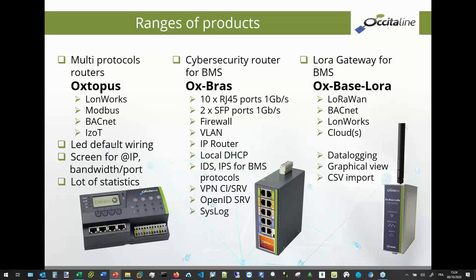The first range is named Oxtopus. Oxtopus is in fact a multi-protocol router with LON, Modbus, BACnet, IzoT, with different advantages, like immediate bandwidth measurement, a lot of statistics on a screen, and also an LED for a wiring fault on each twisted pair. On the twisted pair, in any case, in LON, Modbus, BACnet, IzoT, we measure the capability of the wiring, whether it's wrong or good, and you have a green or red LED.